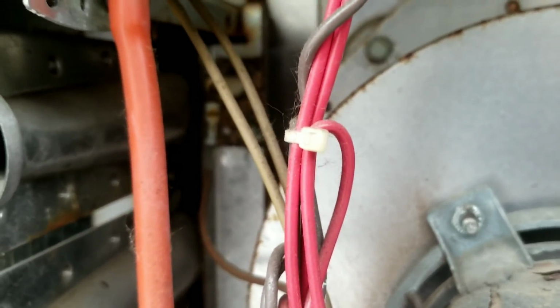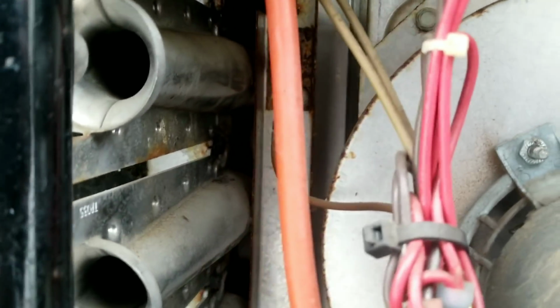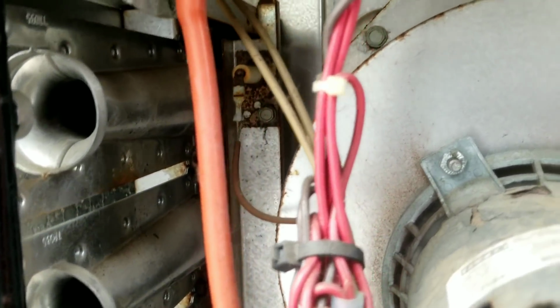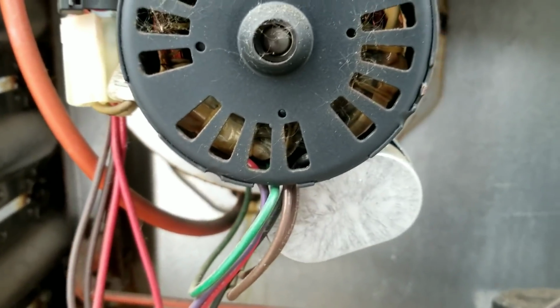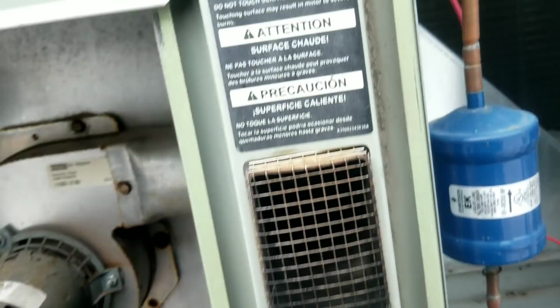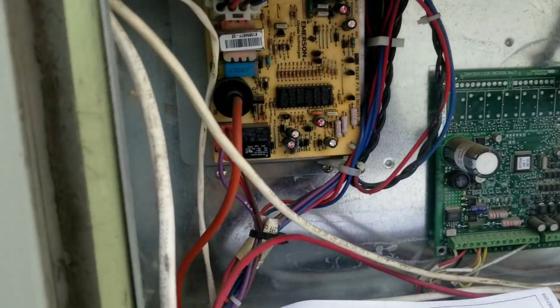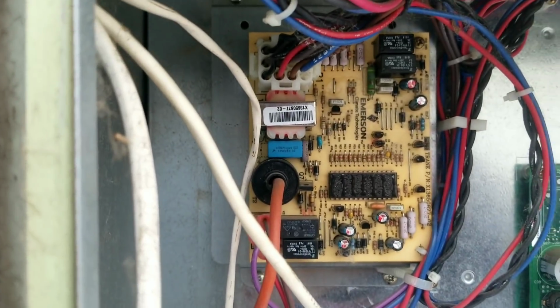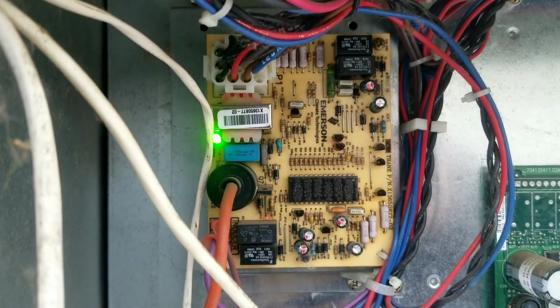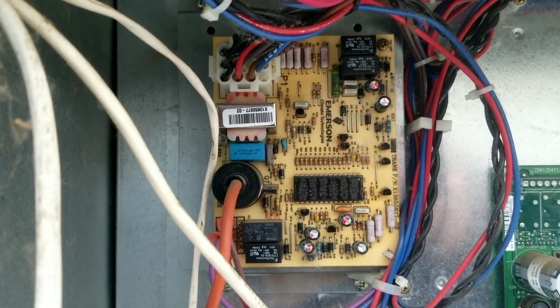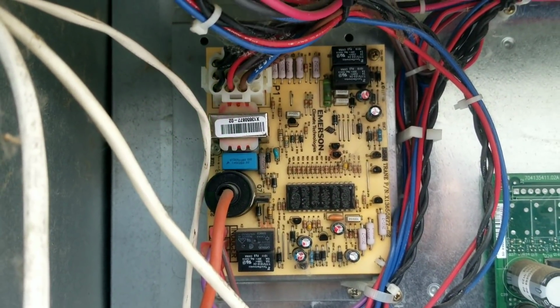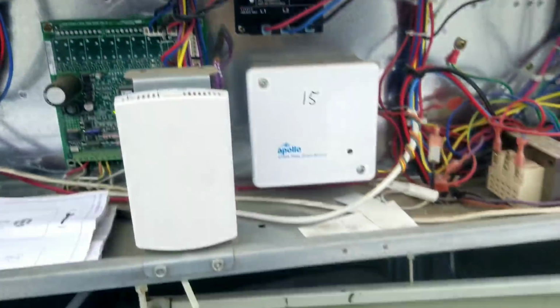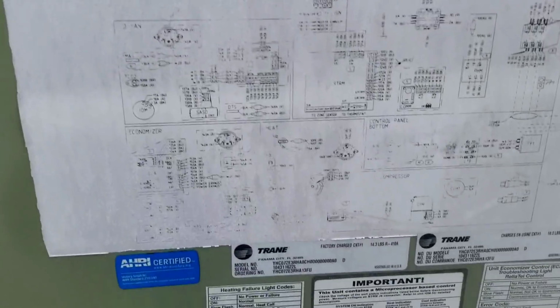Igniter back there, or our flame sensor rather. It's pretty bad. Nice and rusted up. I'll probably end up replacing that along with our sparker. So first things first, let's check out these blinky lights. So we got 6 blinky lights. 6 blinky lights means flame rollout is open. Well, that's no good, is it?